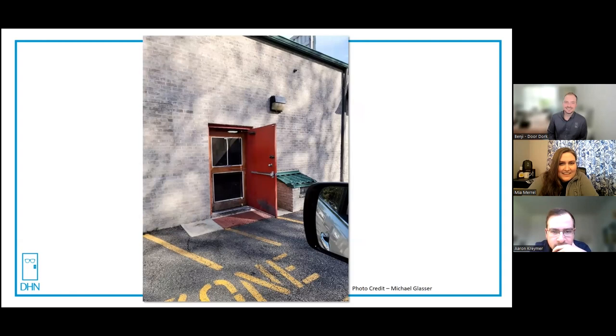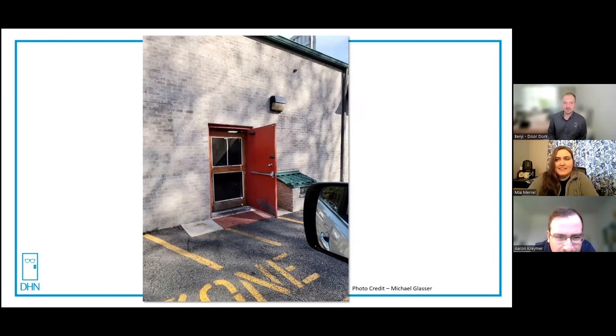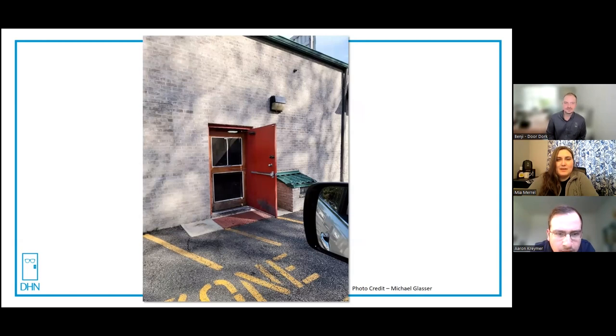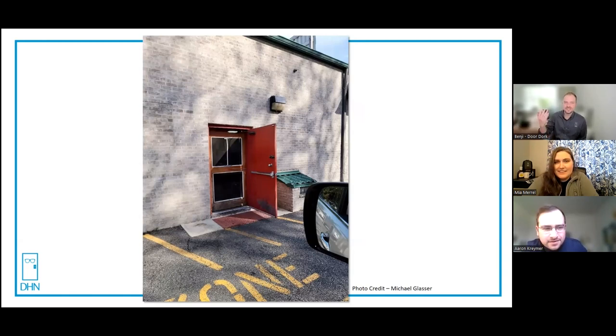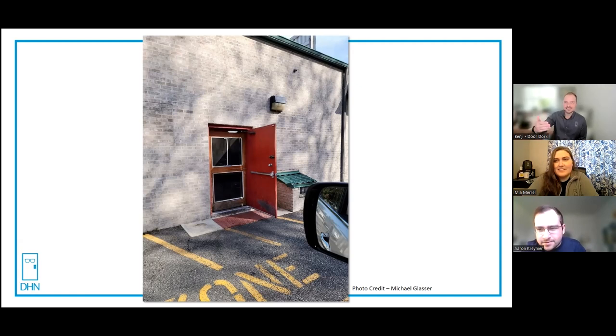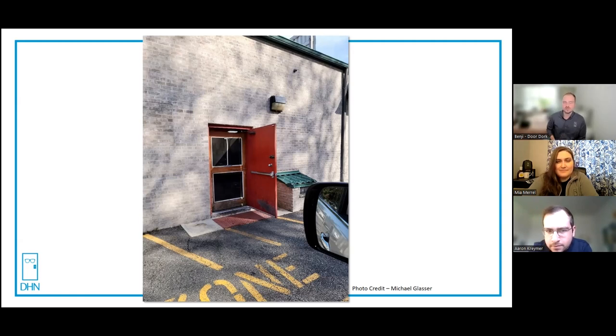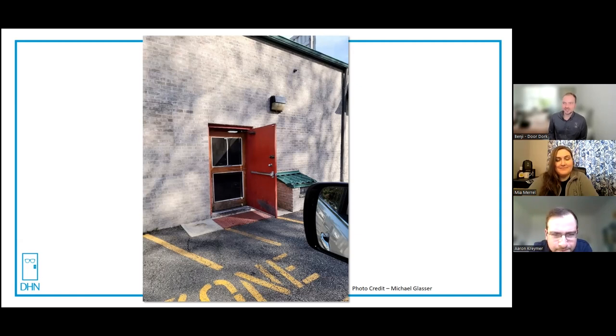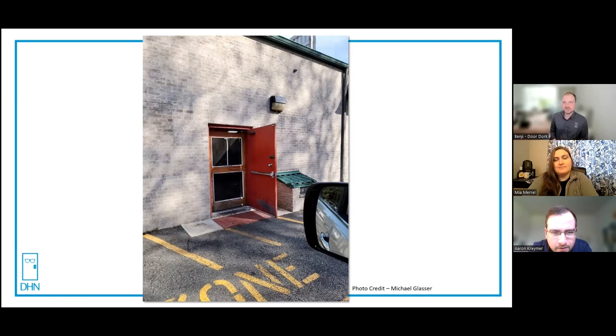Someone takes a second. Okay, what in the world? So, we have an out-swinging exterior door. I confirmed with Michael, this is an exterior exit on the back of a restaurant. And they made a screen door on the inside? Are those like operable windows on top? Yeah, it's like a weather door. Well, it's an in-swinging door in the first place. That's a big no-no on that fire exit because people are just going to run right through that.